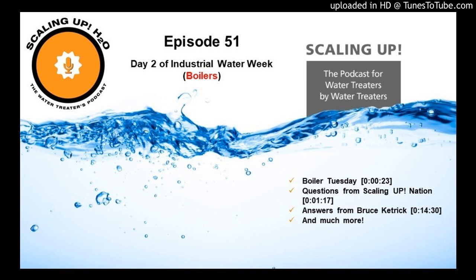The second option that we have is dry storage, and that's more of a long-term solution. There's a whole host of ways that you can do that. I've seen people hang drop lights down in there, for a little bit of heat so the tubes don't condense water. I've seen people put fans in there. There are a lot of products out there today that will vaporize and then form a coating on the metal itself. There's a whole host of ways that you can dry store a boiler. But again, it has to be done properly to the method that you are going to use, or corrosion will take place.